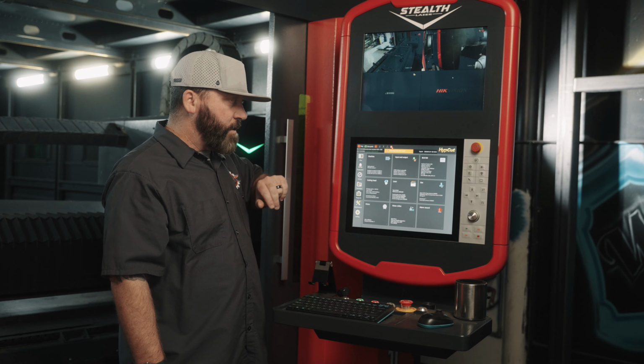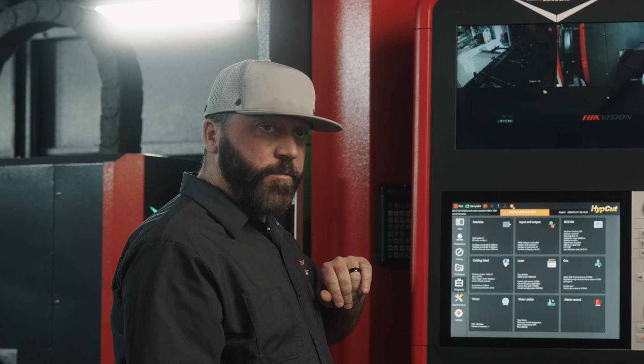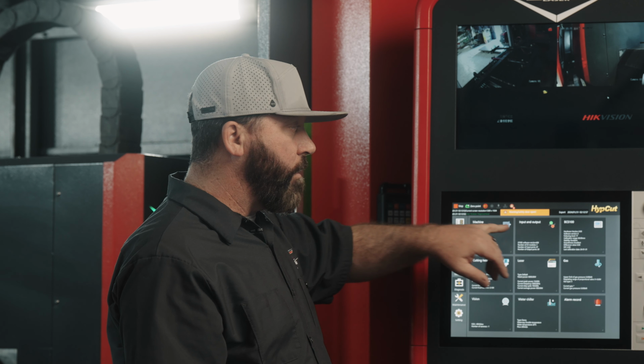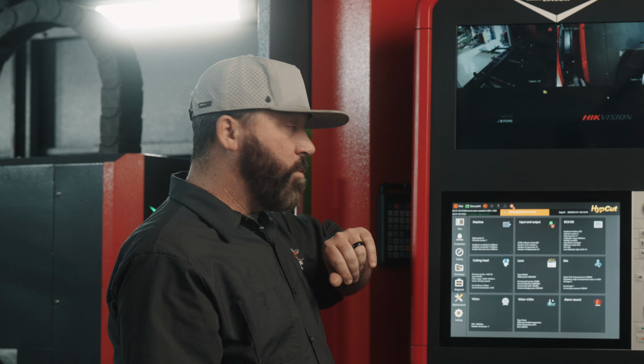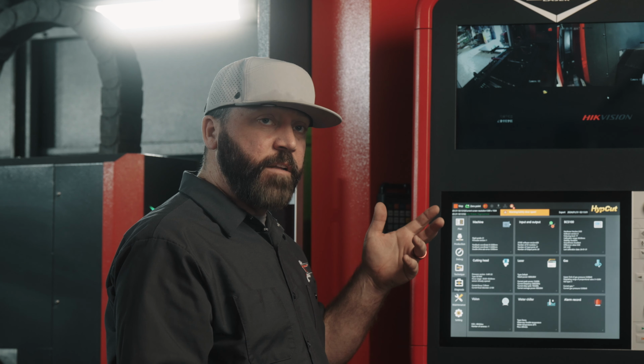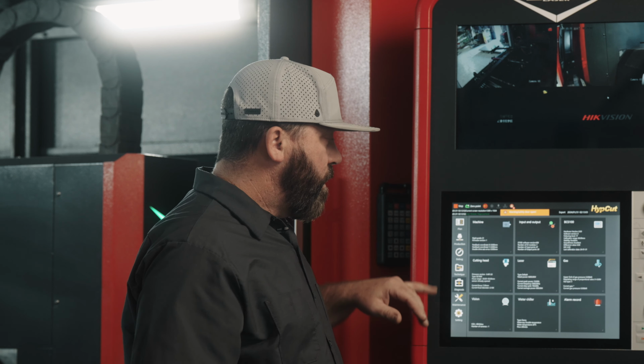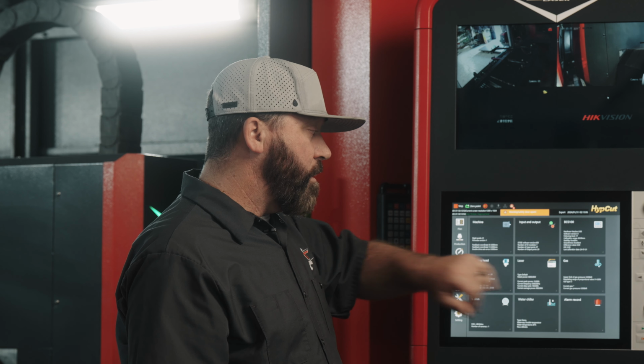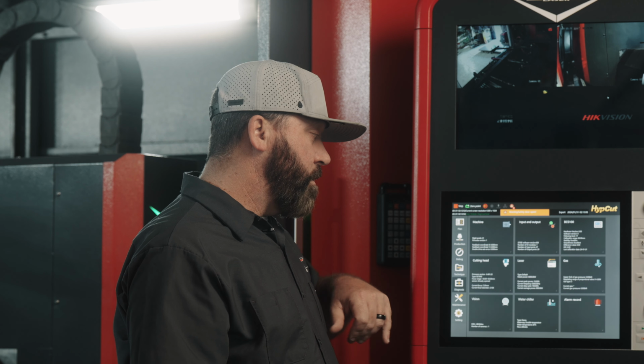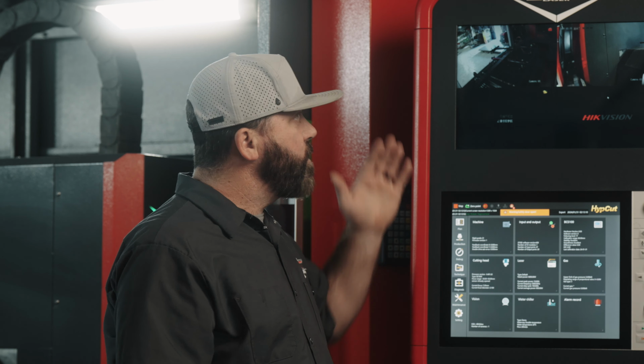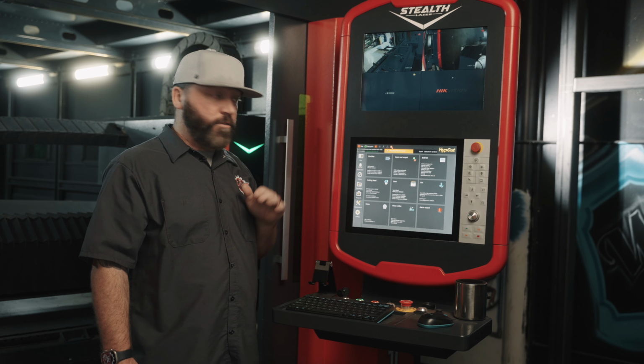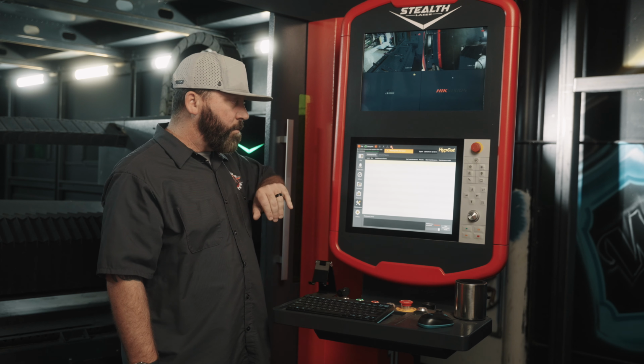We have a diagnostics tab, and inside the diagnostics tab we have all the different categories like machine, our input/outputs, our BCS 100 for our capacitance, which translates into our plate tracking, the cutting head vitals, the laser machine, our gas, any alarms, water chiller, and if we have vision like you see up here to view the machine - those are all integrated right in. We also have scheduled maintenance.